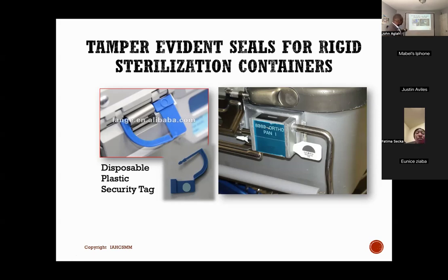So for instance, with a rigid container or blue wraps, we cannot identify the internal indicator after sterilization. It's only the peel pouch, because this side is open. We see everything that is in it. But with that rigid container, after assembly, we lock it. After we sterilize it, we cannot tell if the content is sterile or not. Of course, there are the sterilization records, the external indicator, including this blue dot you see here, and then the tape color change as well. Based on the sterilization record and the external indicator color changes, we can confidently say that the tray has been sterilized.